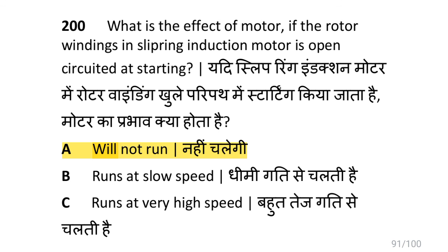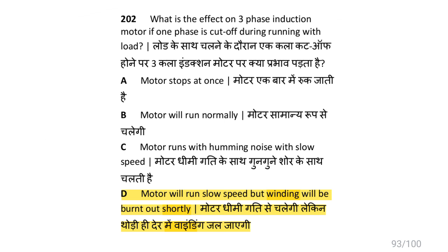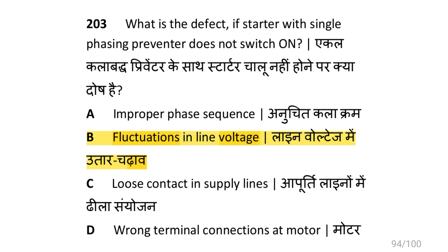If the rotor winding in a slip ring induction motor is open circuited at starting, the motor will not run. If one phase fails during running of a three phase induction motor, the motor runs slowly and finally burns. If one phase is cut off during running with load, the motor will run at slow speed but the winding will burn out shortly.